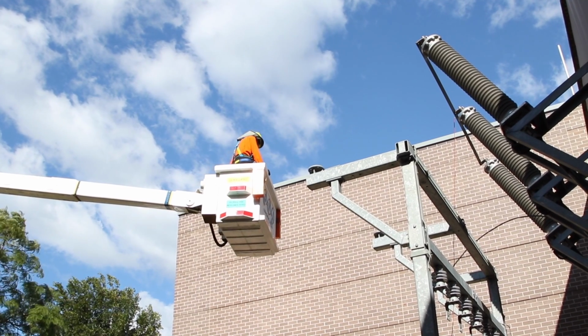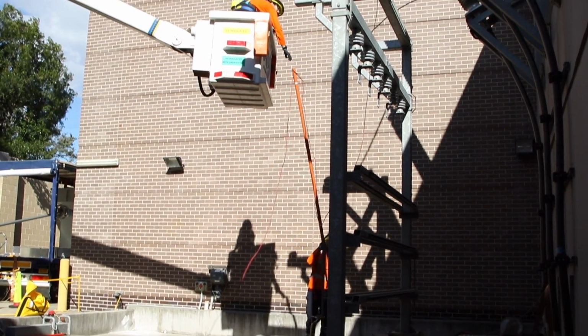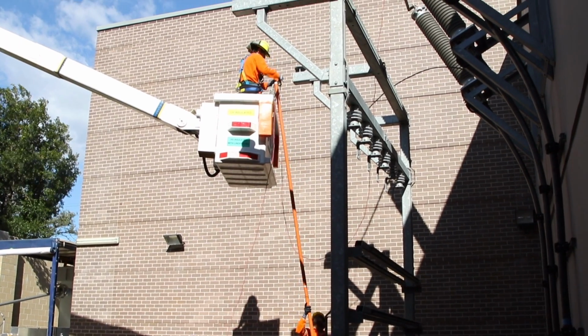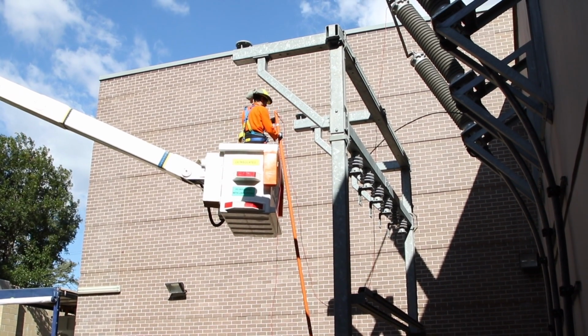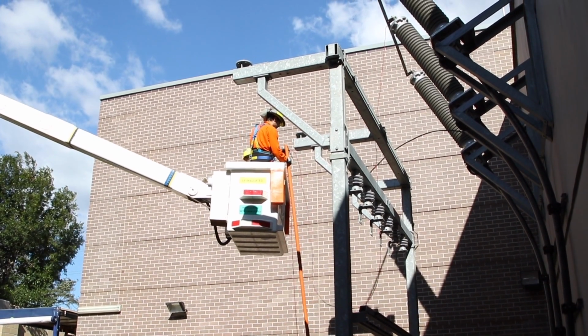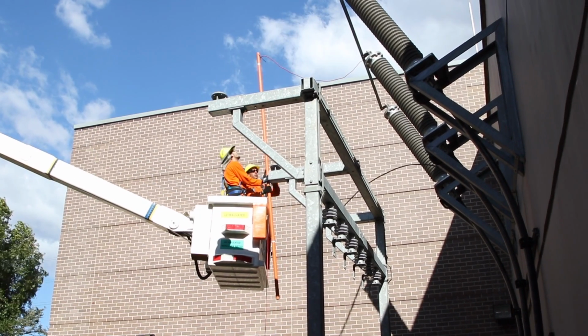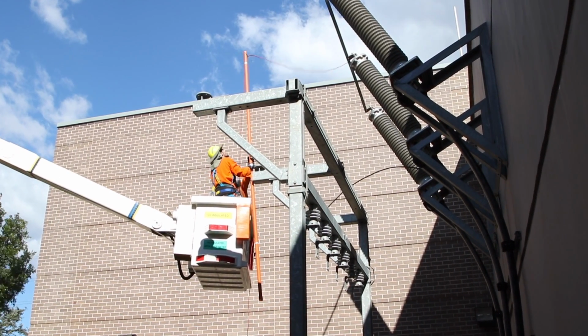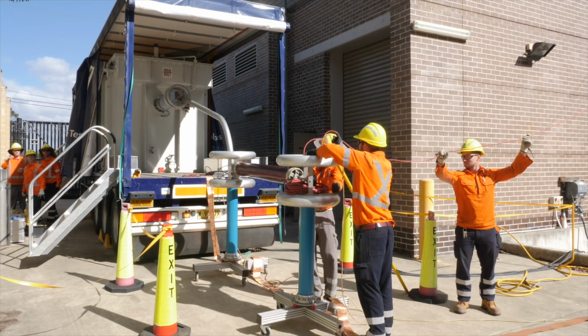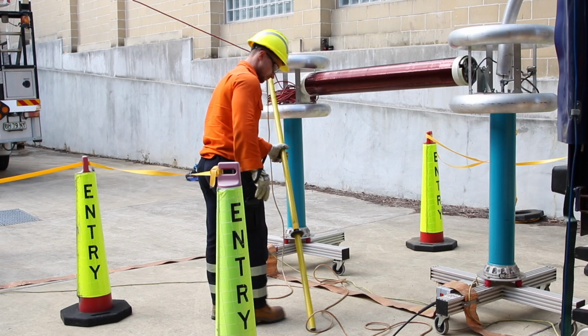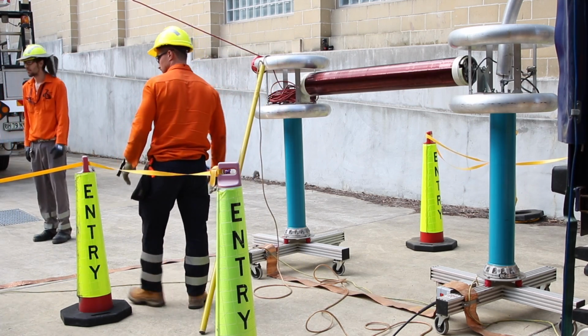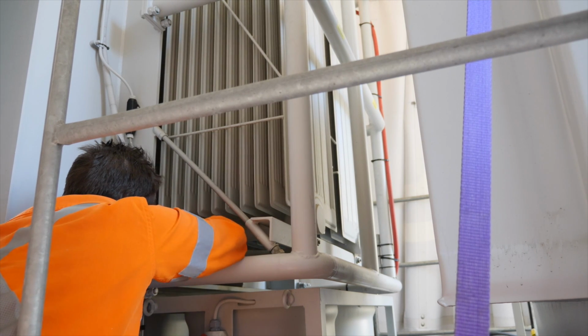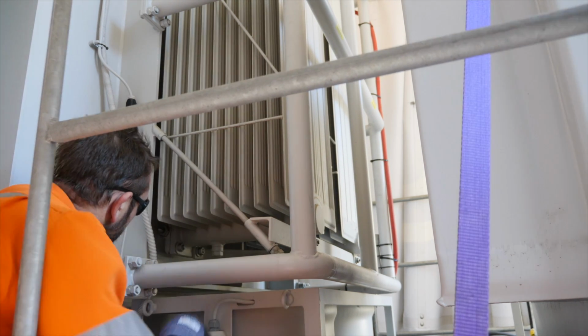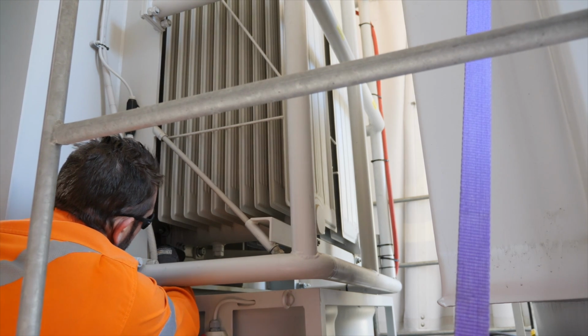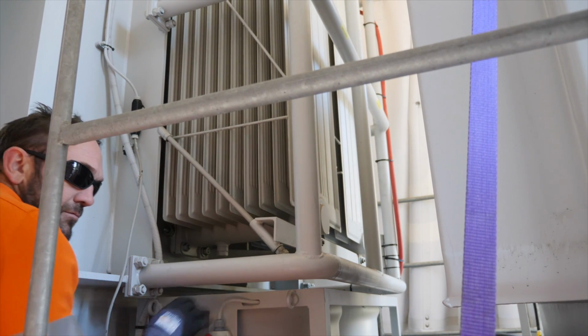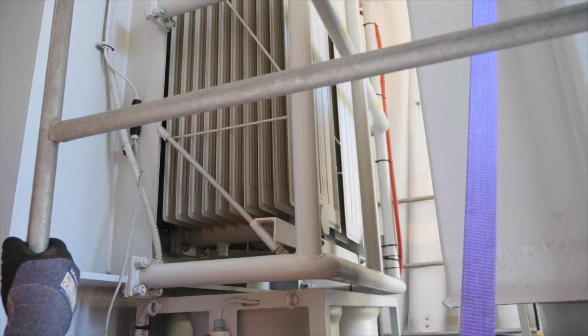The high voltage line used is standard building wire and is held in place by plastic string or conduit to keep necessary clearances from structures and earth for the voltage being applied. The wire is strung between the test trailer output and the test object, and a manual earth will be applied to the test trailer output as a visual indication that the test circuit is earthed. The trailer has an oil-cooled reactor. The reactor's oil radiators are closed during transport and are required to be opened before the test trailer is operated.